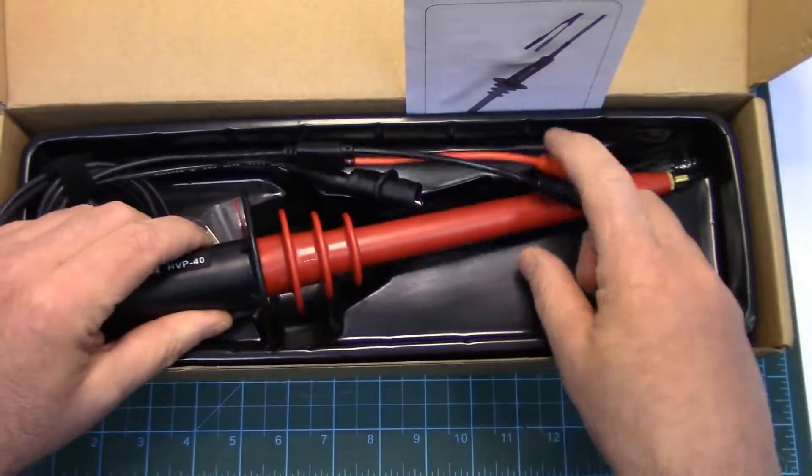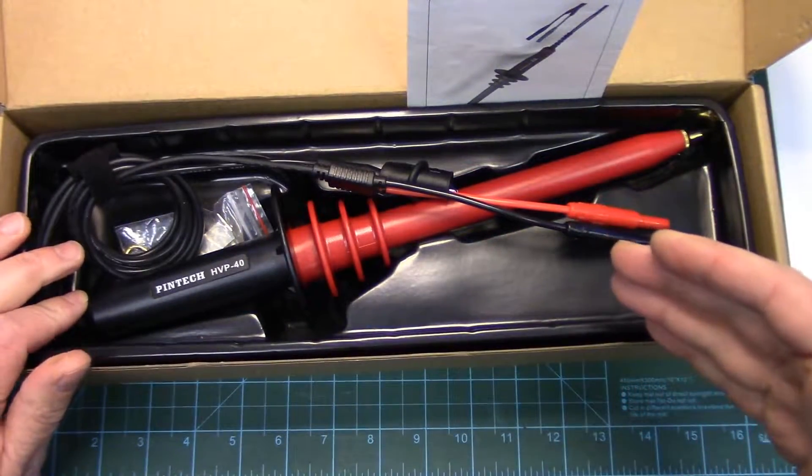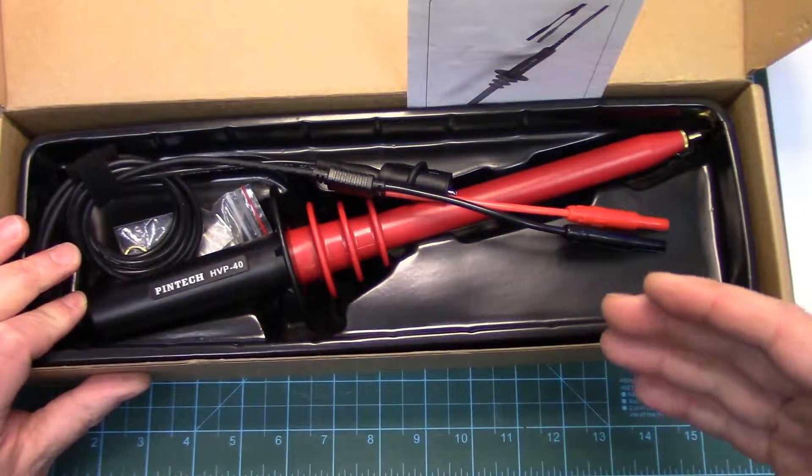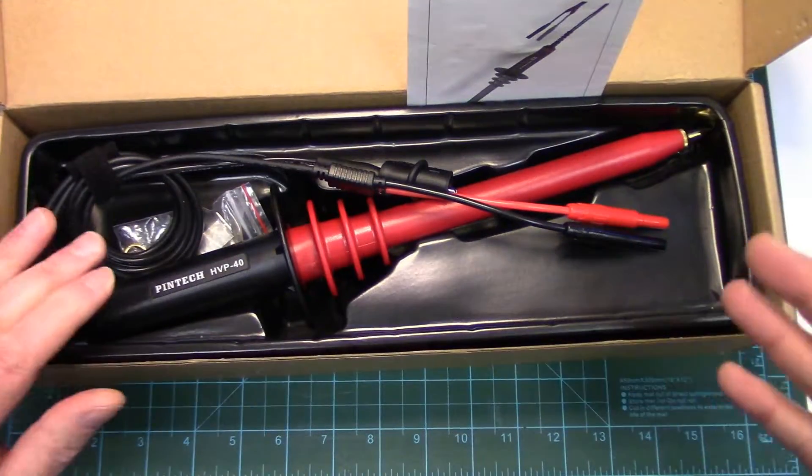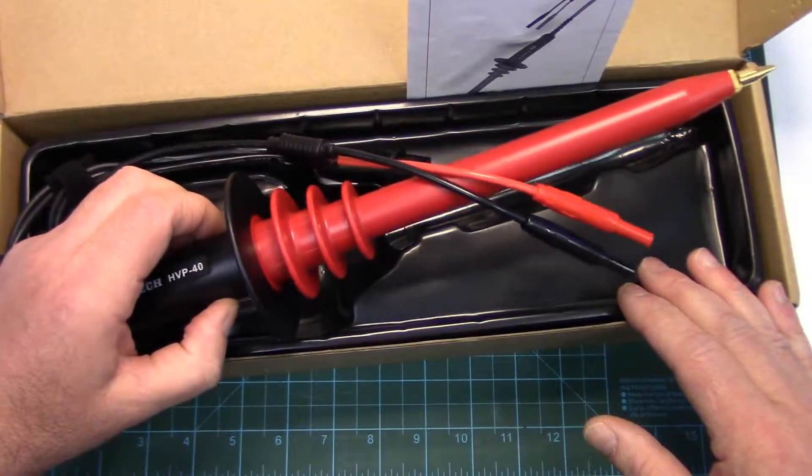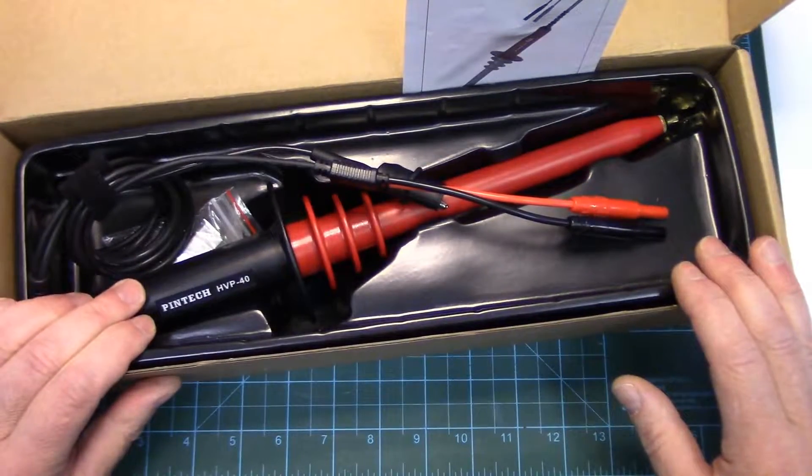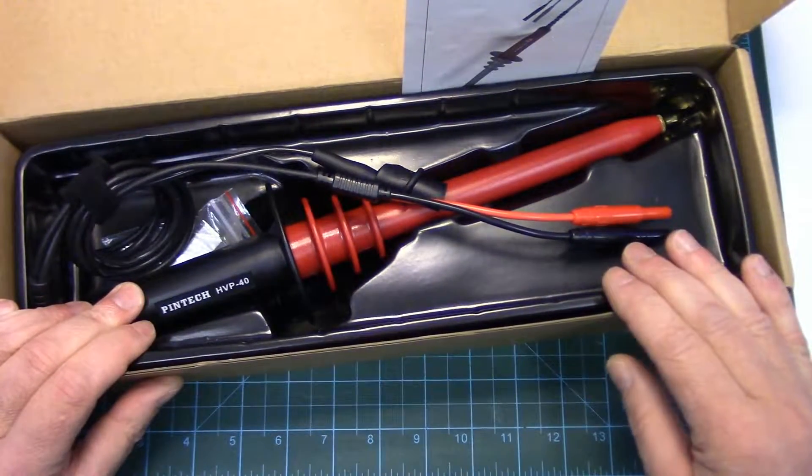These things also double as a high voltage dissipator. So, if you're discharging high voltage capacitance from a CRT or anything that's holding high voltage, when these are grounded, you touch the tip and you can slowly dissipate that high voltage charge through the built-in resistance of these things.